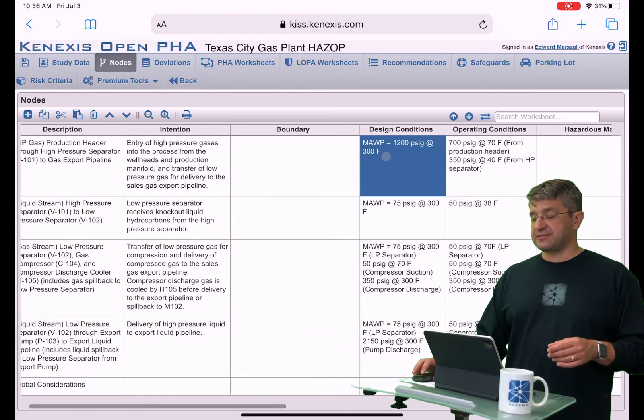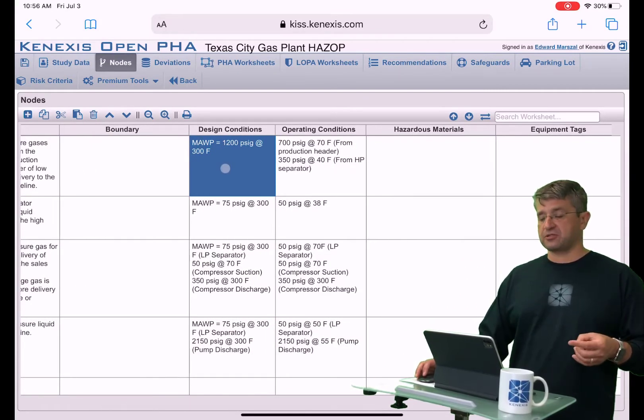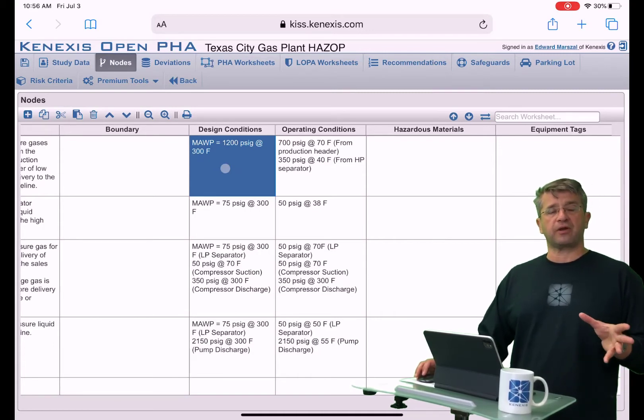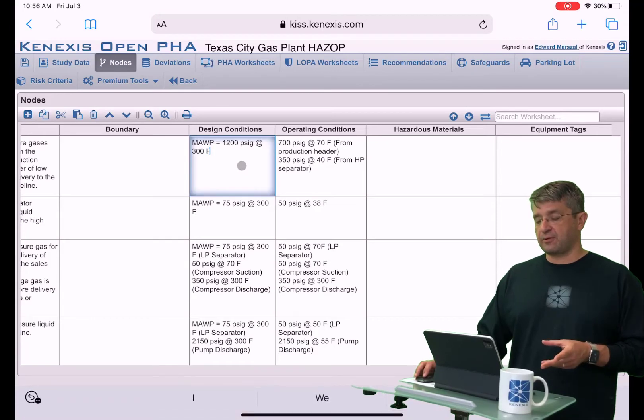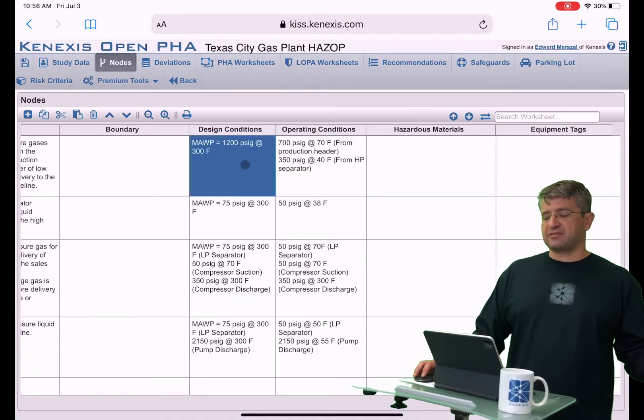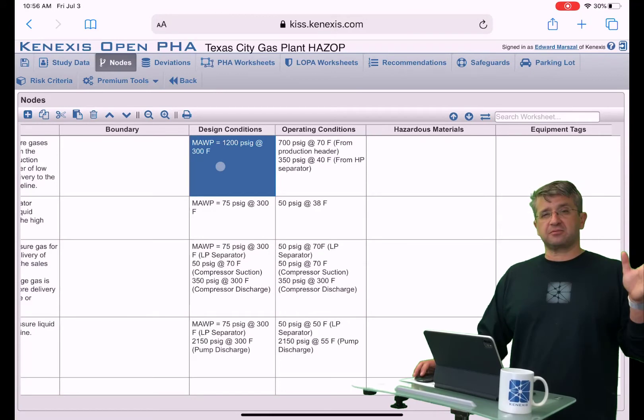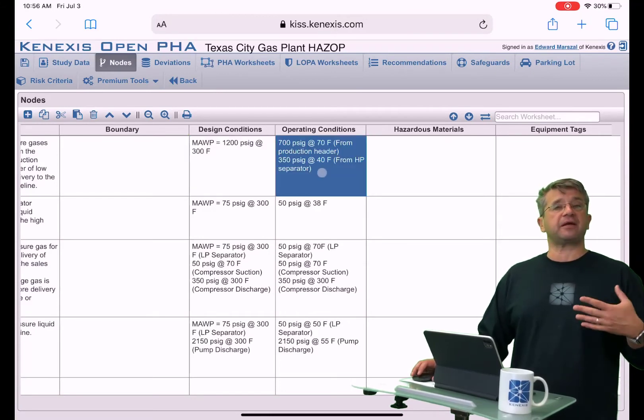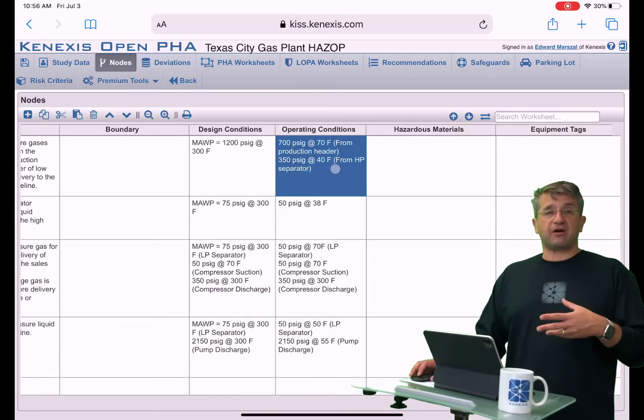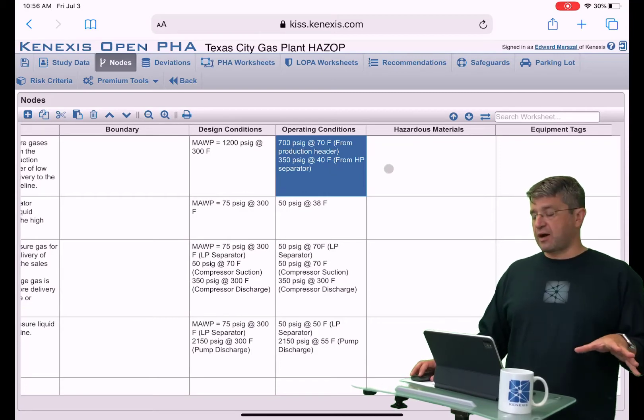Next up is design conditions — operating temperatures, operating pressures, maximum allowable temperatures and pressures. Anything you want to document regarding those types of design conditions can be put here. The complement to design conditions is the operating conditions. Design is what your maximum limits are, versus operating conditions, which is where you typically expect to run. You can even document the operating conditions associated with different modes of operation here.